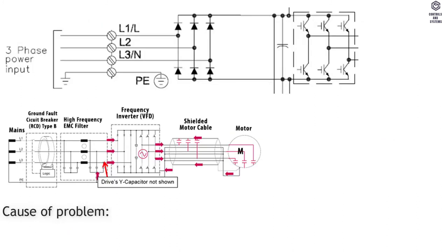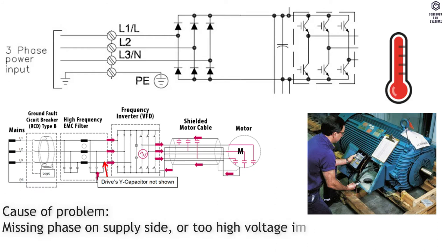Warning, Alarm and Trip Lock 4: Mains Phase Loss. Cause of Problem — missing phase on supply side, or too high voltage imbalance. Check supply voltage.